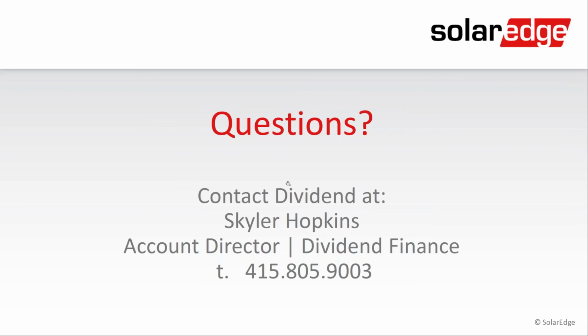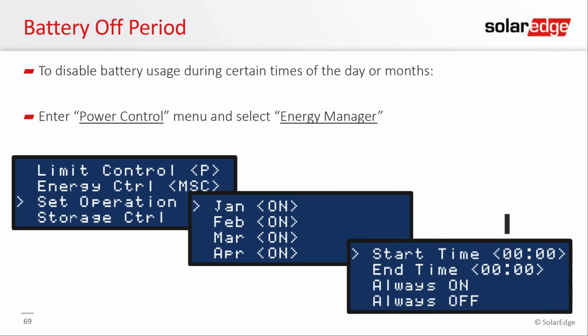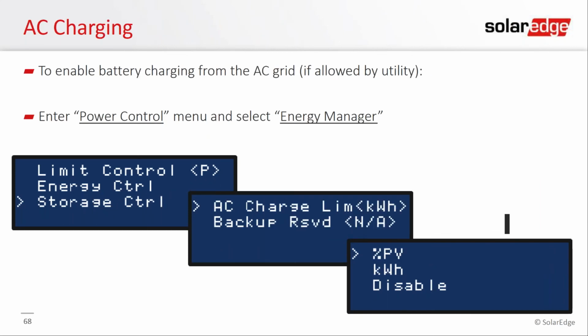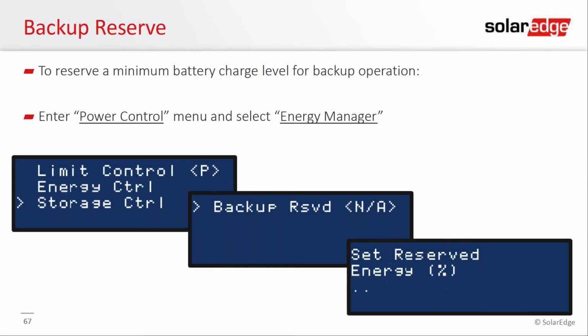And of course, this overrides all TOU settings, and we're just going to maximize the consumption of the battery. So we're only going to discharge it to meet home loads if solar isn't present. The reserve allows us to keep a little bit extra in the tank. So if you wanted to think about it, it's kind of a multimodal inverter in which we can run time of use when grid connected and then run backup when not grid connected.